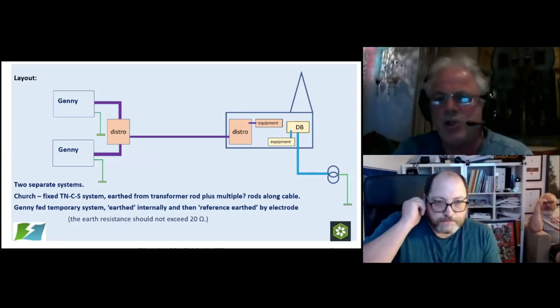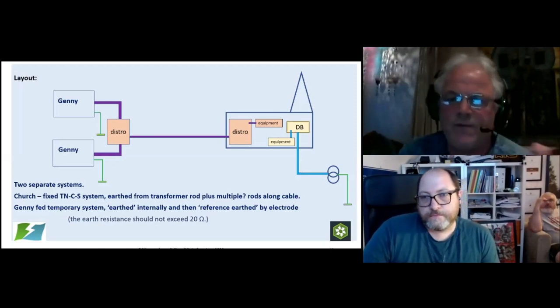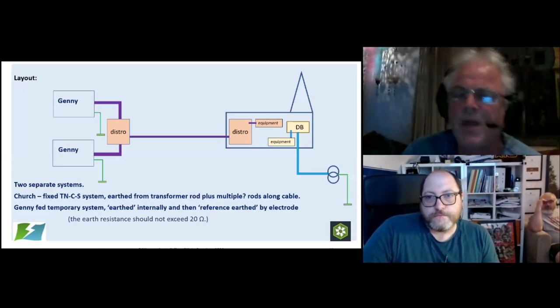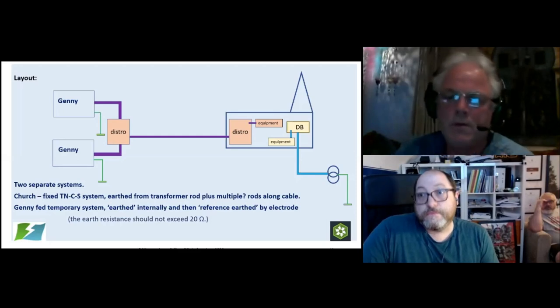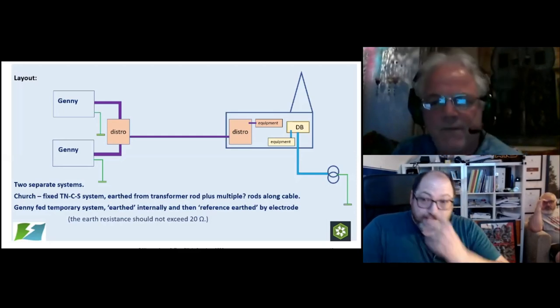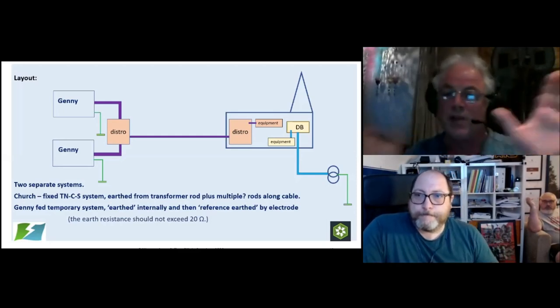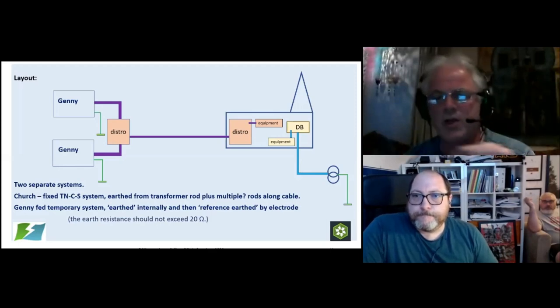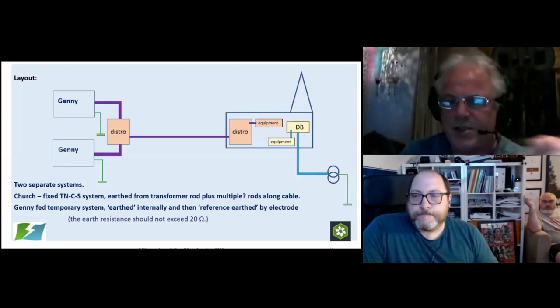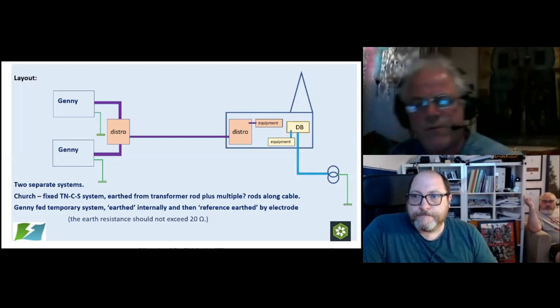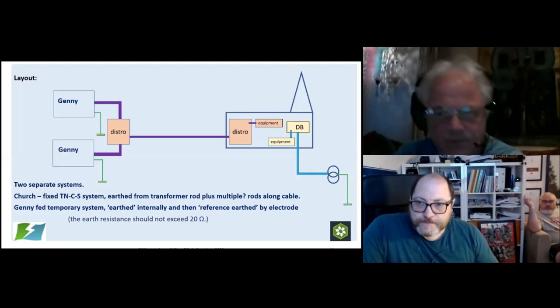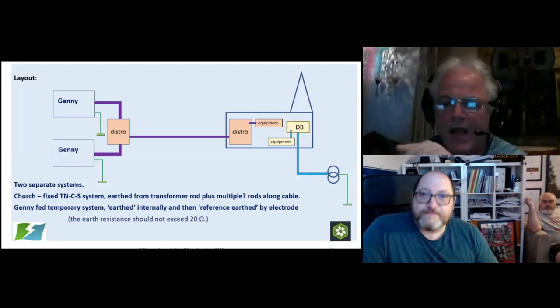Now, the issue is that some of the equipment fed off the temporary distro could be very close to some of the equipment fed off the fixed installation, so there could be simultaneous contact. You've got a different earthing system. You've got an earthing system from the generator, and you've got an earthing system from the TNCS from the transformer earth electrode.